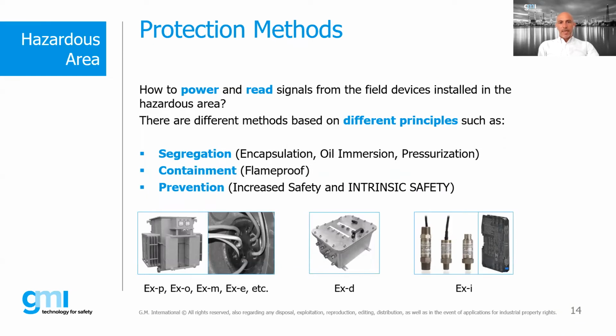So you can see here how to power and read the signals from a field device installed in the hazardous area. There are different methods, as we said. Principle, segregation, so it can be encapsulation or immersion or pressurization, where you have Ex p, Ex o, Ex m, Ex e applications. You can also have containment, called flameproof, Ex d, the big housing especially. And the prevention, where we can allocate increased safety and intrinsic safety. Where we are.